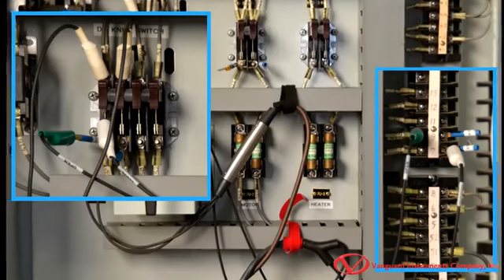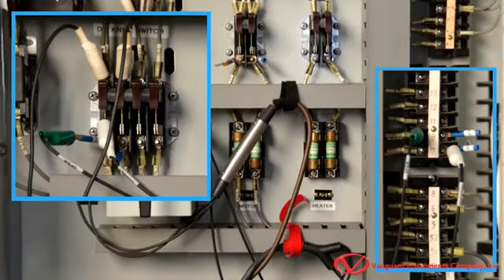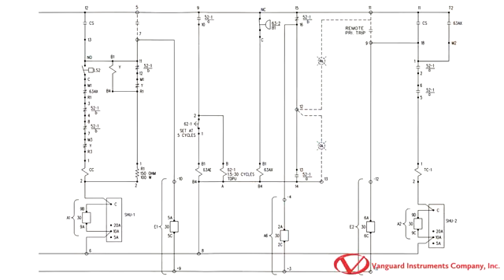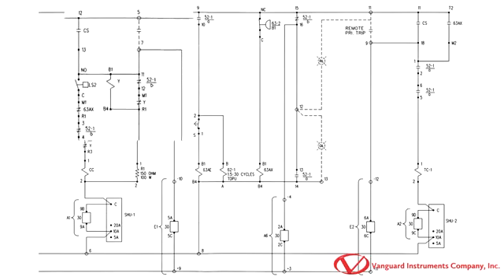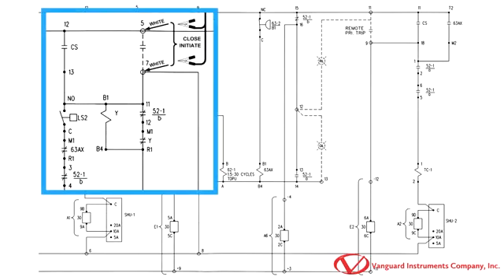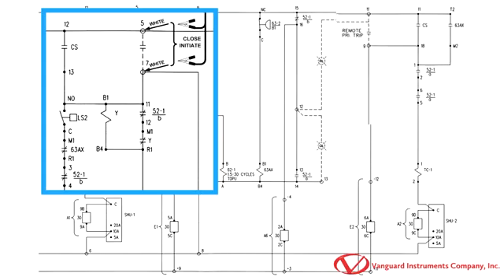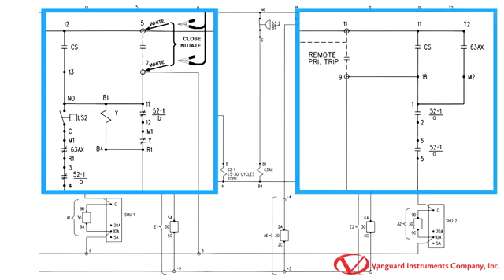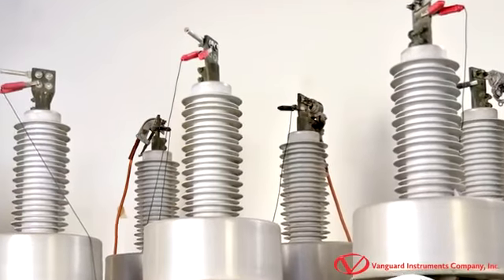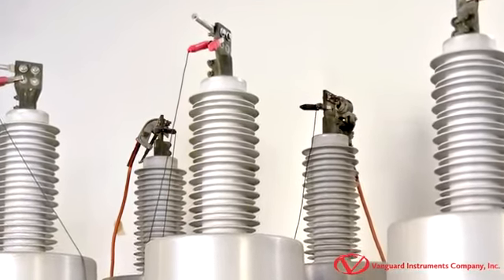The initiate circuit acts like a switch to energize the trip or close coil. In this illustration, the initiate circuit will connect terminal 5, which is the positive DC source, to terminal 7 of the circuit breaker closed circuit. On the trip circuit, the initiate circuit will connect the positive DC supply to terminal 9 of the trip circuit. Once you have made all cable connections, remove the ground cable from one side of the breaker.